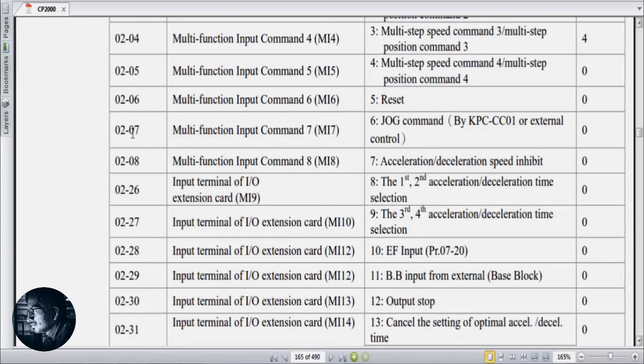Then parameter 02-07, multi-function input function setting — we set this to 42 for auto switch. The parameters are now done and we have completed all the settings. The drive is ready to run.